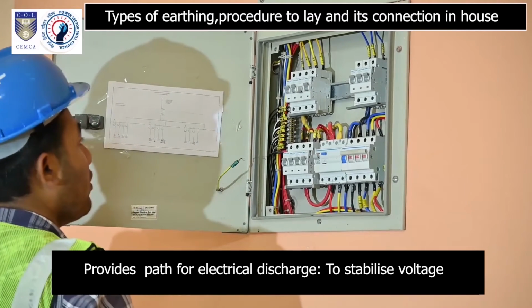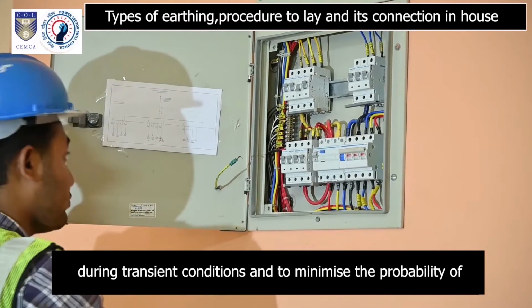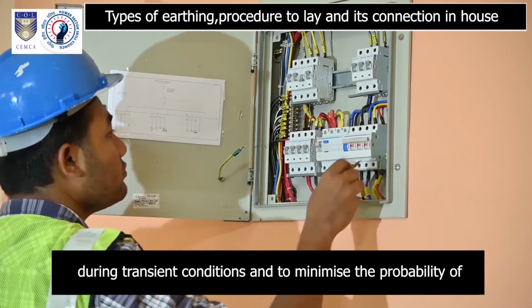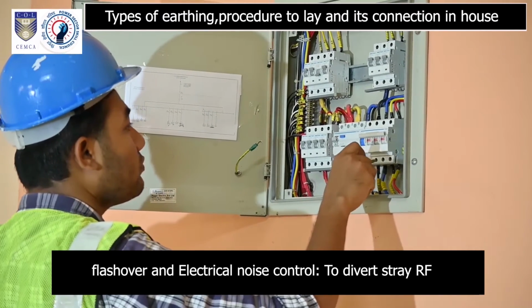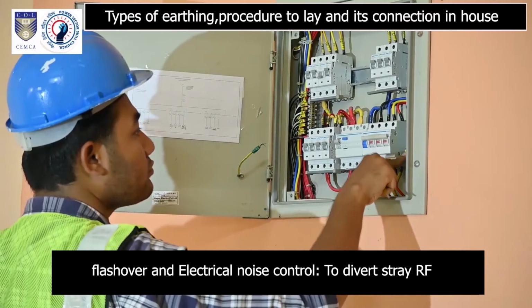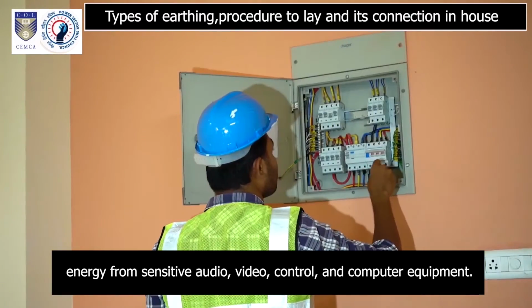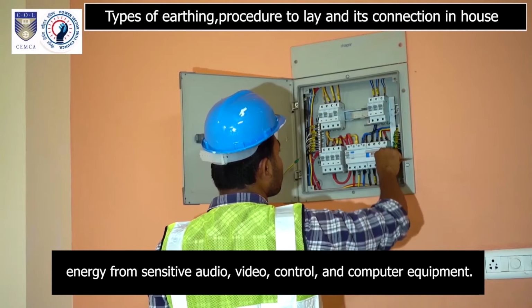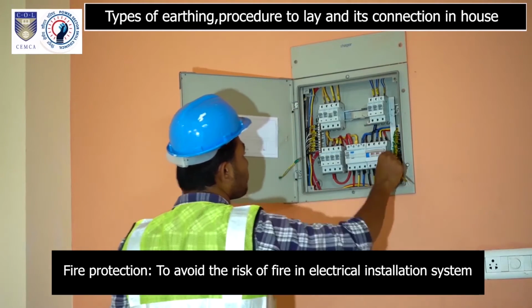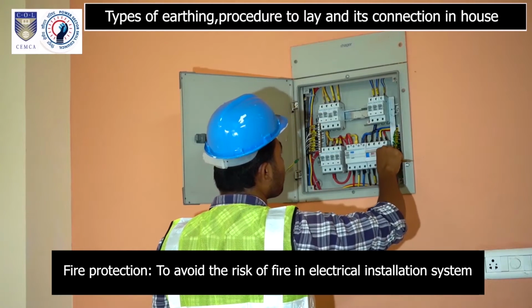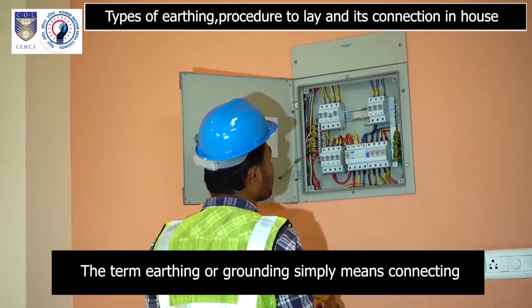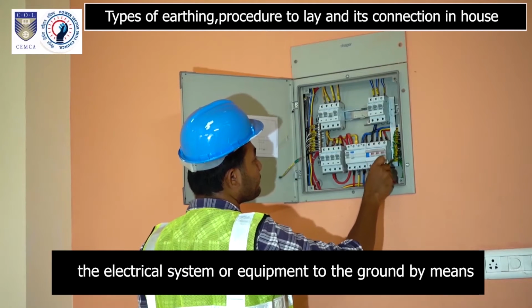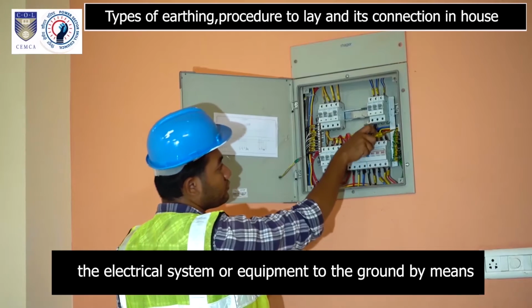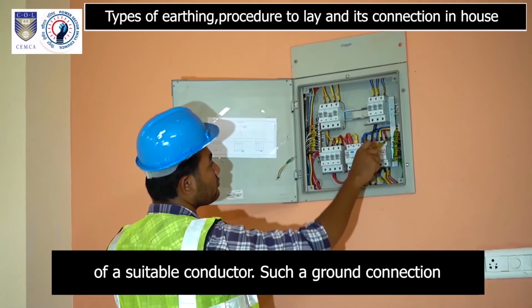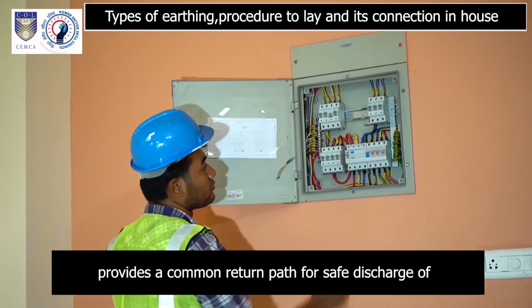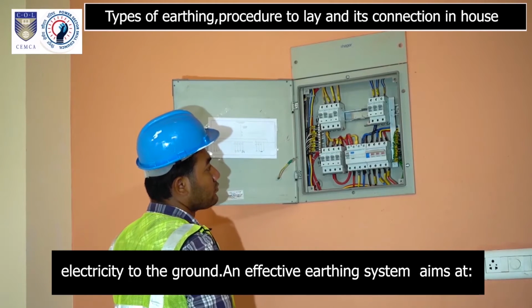Provides a path for electrical discharge, to stabilize voltage during transient conditions and to minimize the probability of flashover, and electrical noise control, to divert stray RF energy from sensitive audio, video, control and computer equipment. Fire protection, to avoid the risk of fire in the electrical installation system. The term earthing or grounding simply means connecting the electrical system or equipment to the ground by means of a suitable conductor. Such a ground connection provides a common return path for safe discharge of electricity to the ground.